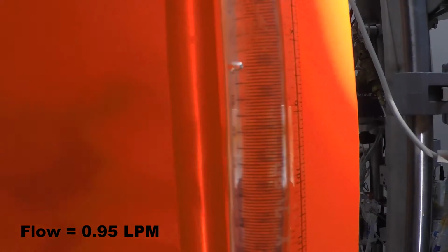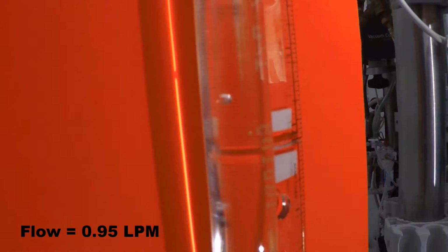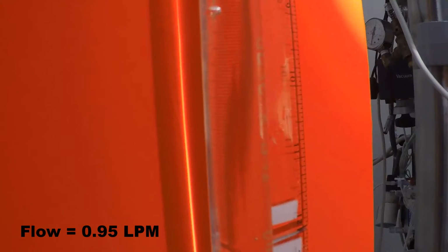Viewed again from a side angle, we see how buoyancy causes the bubble to slip away from the stronger viscous drag forces of the central lamina and into a zone of nil flow, making it appear as if it is neutrally buoyant and floating in a stationary fluid. But when the tubing is struck with a clamp, notice how the generated turbulence is able to pull the bubble back into the central lumen against where the flow is highest, carrying the bubble downward in the flow until buoyancy causes the bubble to fall out again and rise.